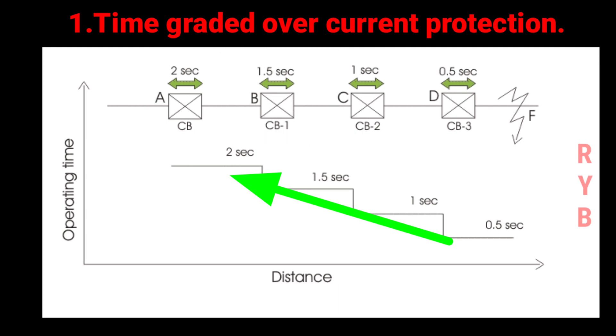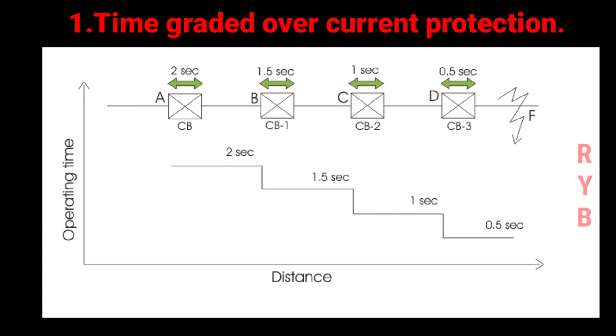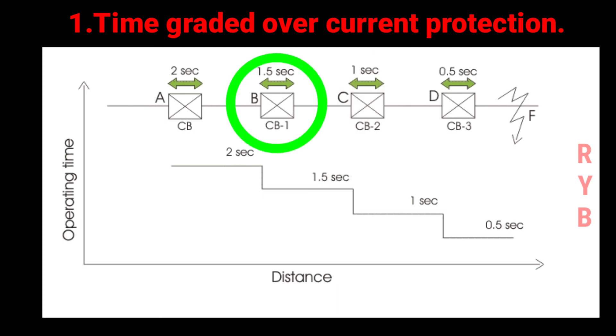Now assume a fault occurs at point F. Due to this fault, fault current flows through all the current transformers connected in the line. Since the relay at point D has the minimum time setting, circuit breaker CB3 will trip first to isolate the fault zone. If CB3 fails to trip, the next relay with a higher time setting will operate and circuit breaker CB2 will trip. If CB2 also fails, circuit breaker CB1 will trip to isolate a major portion of the line.